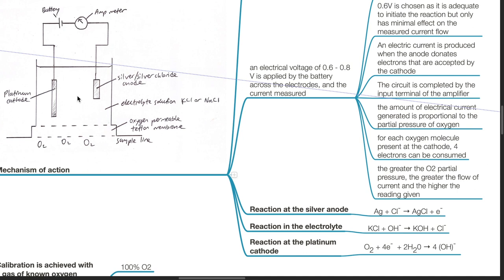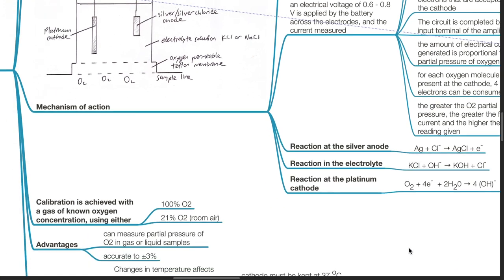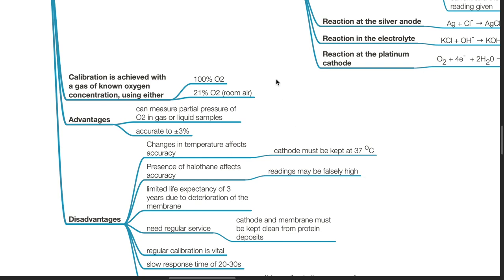The greater the oxygen partial pressure, the greater the flow of current and the greater the reading given. Reaction at the silver anode: Ag plus Cl- becomes AgCl plus electron. Reaction at the electrolyte: KCl plus OH- becomes KOH plus Cl-. Reaction at the platinum cathode: O2 plus 4 electrons plus 2H2O becomes 4OH-. Calibration is achieved with a gas of known oxygen concentration using either 100% oxygen or 21% oxygen, also known as room air.